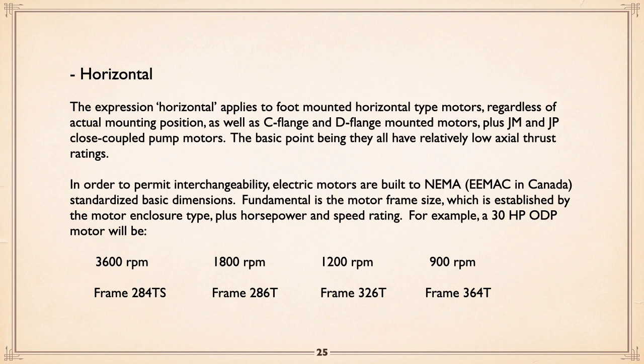Pardon me. Now, frames. It varies with the horsepower, but here's a 30 horse open drip proof motor. At 3600 RPM, it's a frame 284 TS. The S stands for short shaft. That means basically that you can't have a whole lot of radial load, like belts, for example. There isn't enough shaft there to permit you to put a belt on. From there on into standard, 1800 RPM, it's a 286 frame, 1200, 326 T. You can see how the frames get larger and larger because the motor is bigger, because the horsepower the motor has to put out means more torque, because horsepower is a combination of torque and RPM. The RPM's going down, so the torque has to go up, which means the motor size has to go up, and the frame has to be bigger.